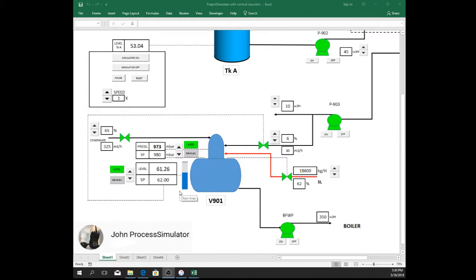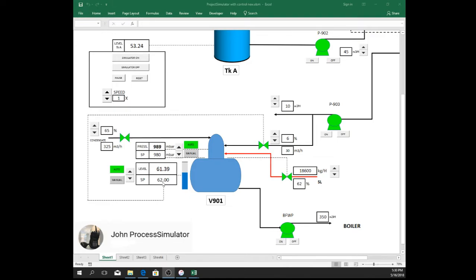Let's say the actual level now is 61.29. Since this is now in auto, the level will be maintained within the range of setpoint 62% by increasing or decreasing this control valve. So now the opening is 6%.